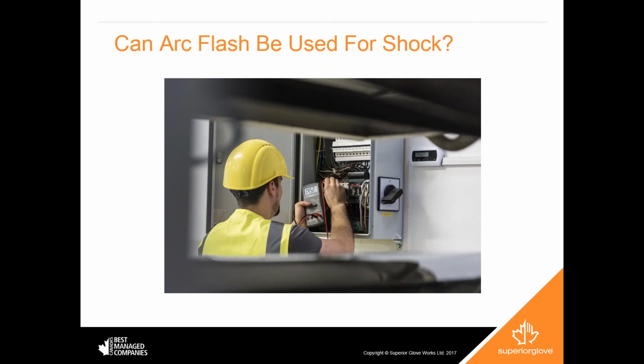So even a low voltage electrical glove with a leather protector on it is going to give you a combined arc rating. But again, as we mentioned earlier, you're talking about gloves that are much thicker and obviously make it very difficult for a maintenance person to do their work on a machine when they have to.